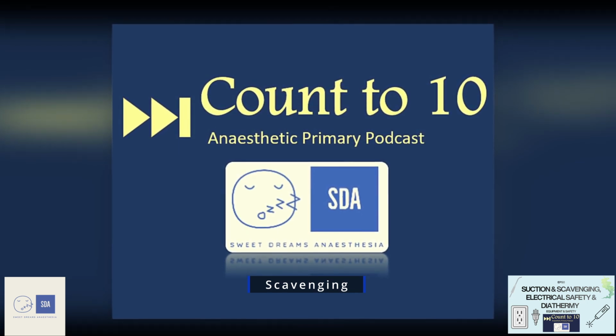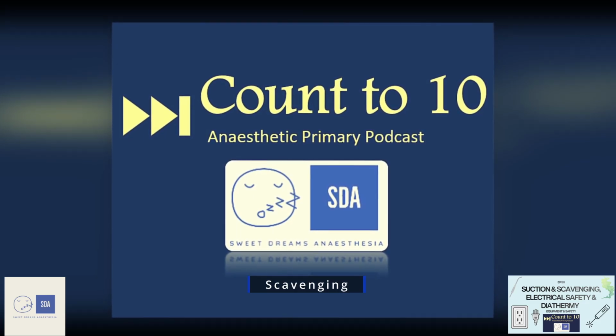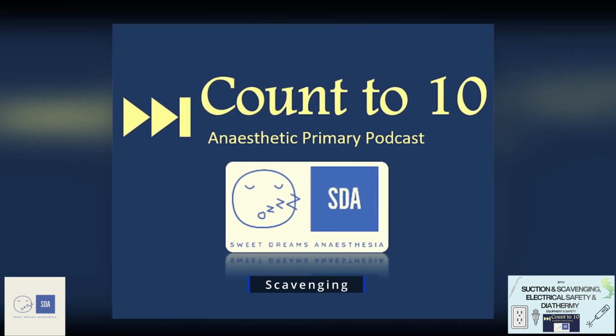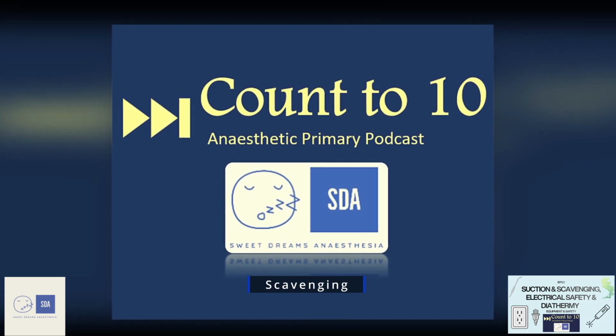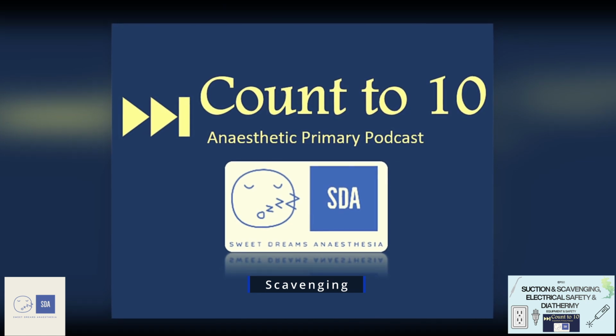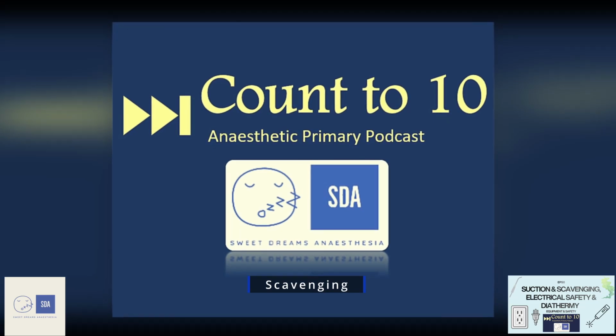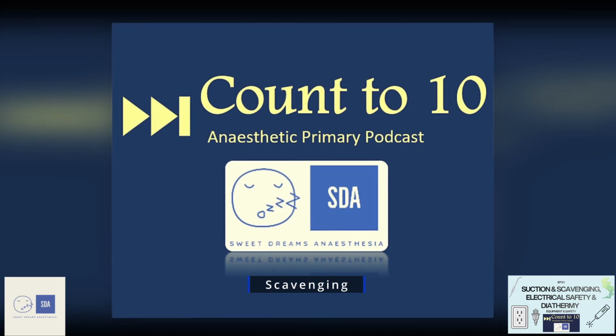The reason we want to decrease their exposure within the operating theatre is because different countries have different safety guidelines on how much exposure we should be having from each certain gas. In the UK, they recommend over an 8-hour period, you should have less than 100 parts per million exposure of nitrous oxide, less than 50 parts per million exposure of isoflurane, and less than 20 parts per million exposure of sevoflurane. The reason these guidelines come about is because there's some linkage between higher exposure and increased chances of infertility, miscarriages, increasing the rate of certain cancers, and congenital abnormalities. The overall evidence for all of this is low, but this is why scavenging is an important safety part of our curriculum.